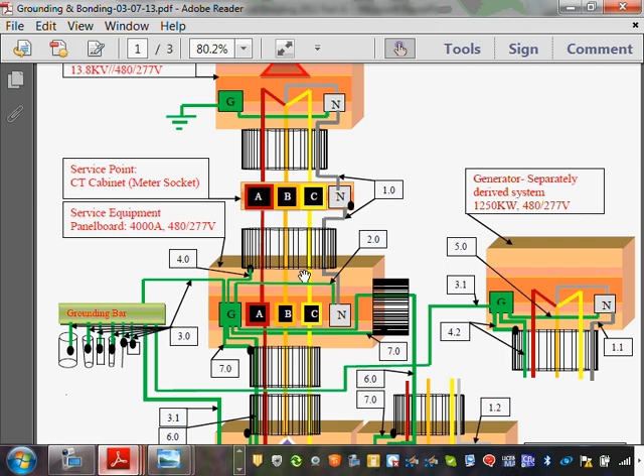So my CT cabinet here, my meter socket, what else? CT cabinet, meter socket, termination box, they call it. You probably heard all these terms. I can ground it using the neutral, right? Because that's a metallic box sitting outside. I need to ground it. How are you going to ground it? You can use the neutral that's coming from the utility and use it as an equipment grounding conductor, believe it or not, as an equipment grounding conductor, and ground the CT cabinet. Why? Because you're on the line side of the service disconnect means, so-called.